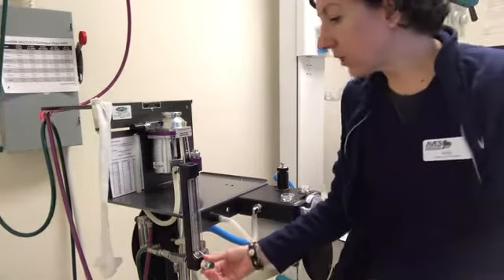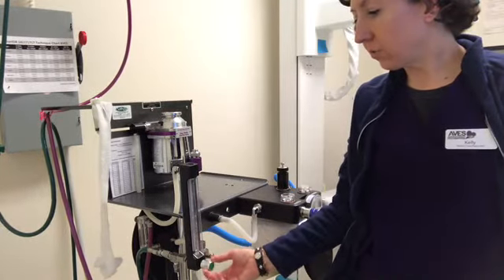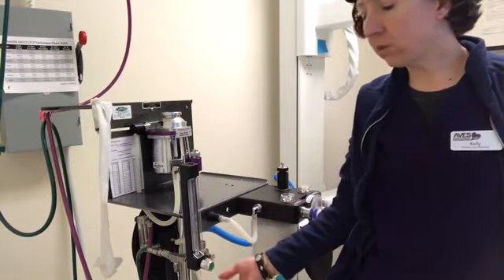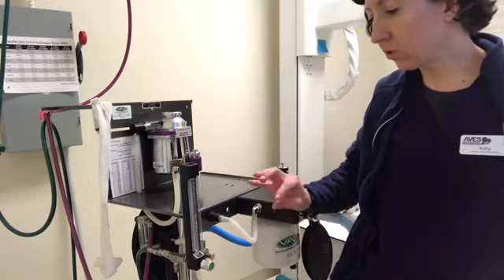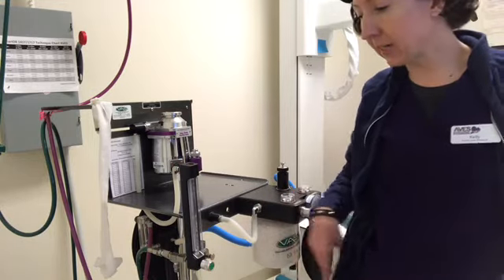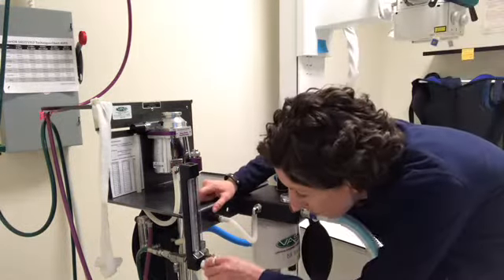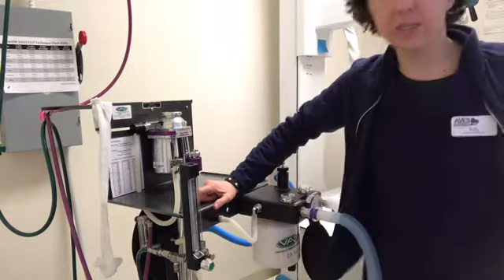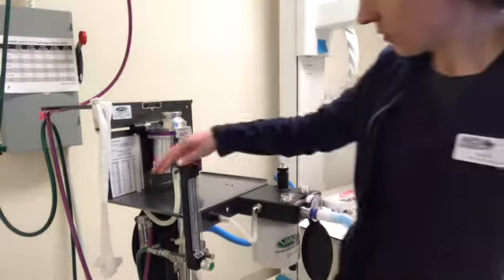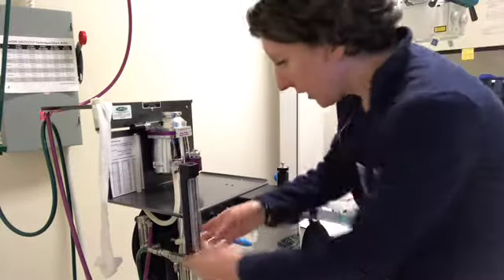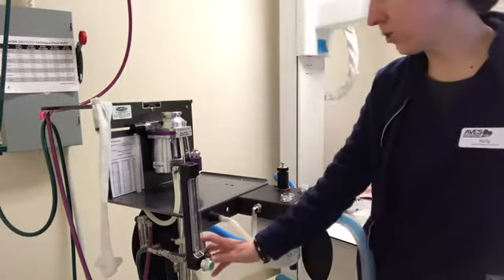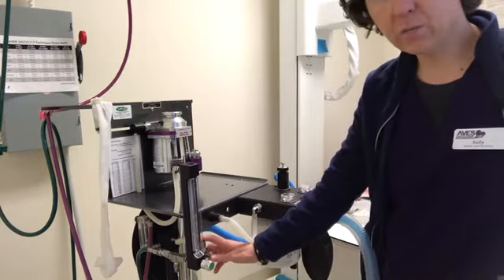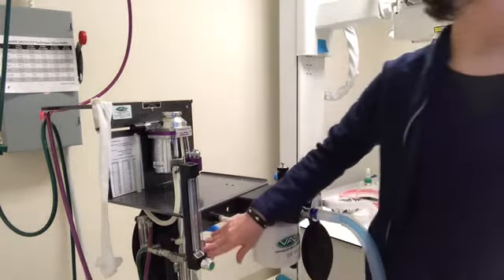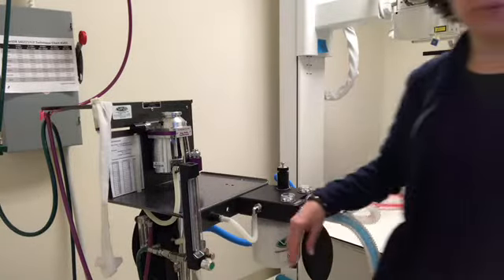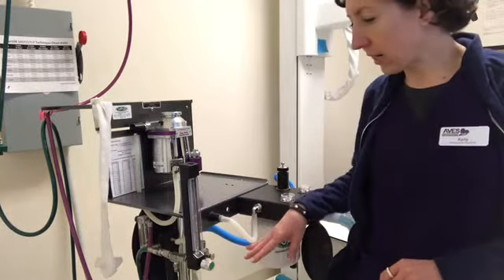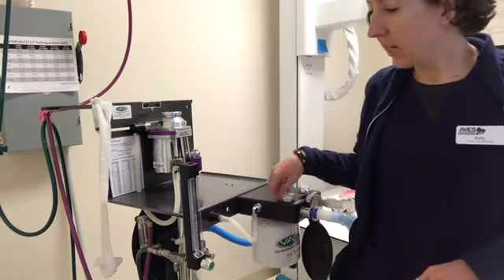Now on the flow meter, when you turn it to the right to turn it off, you want to be real delicate about it, because if you turn it too hard, it will break the stem inside the system. So basically, you just want to turn it until the ball gets down to 0 liters per minute. Then leaving the flow meter, it goes right next door to the oxygen flush valve, which is this little button down here. The oxygen flush valve rapidly delivers large volumes of oxygen to the patient, and it is pure oxygen.